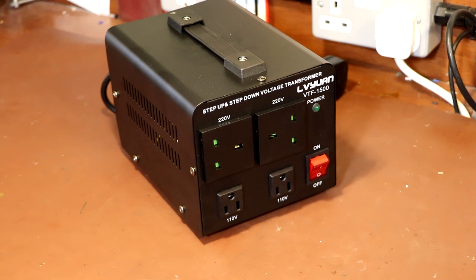The rated output power for this particular piece of equipment is 1500 VA, and it's important to say that's a VA rating, so that's apparent power. The VA rating of this device really comes down to the size of the transformer and its efficiency. The more money you pay, the bigger the transformer and the higher the VA rating it will have.